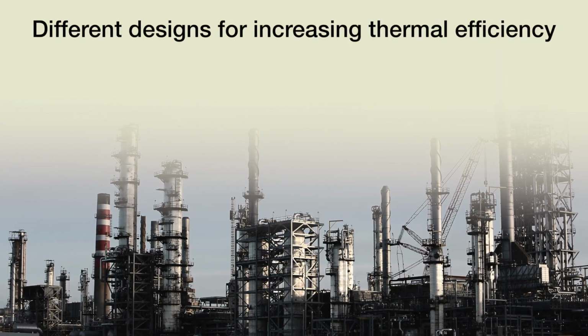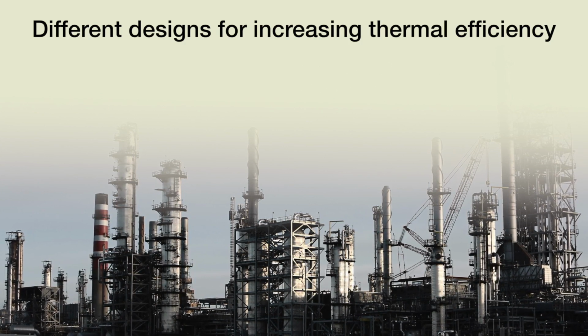After components and working principle, now we should concentrate on increasing the efficiency of the combined cycle power plant. Several optimization studies and research were carried out and new technologies were developed to eliminate carbon dioxide and improve the thermal efficiency for the same fuel flow rate used in traditional cycles. So, our purpose is to minimize the emission of polluting gas and increase the gas turbine mass flow rate used in a steam injection system, which permitted an increase of gas turbine cycle efficiency of about 0.11% for each 1% of the steam injected.